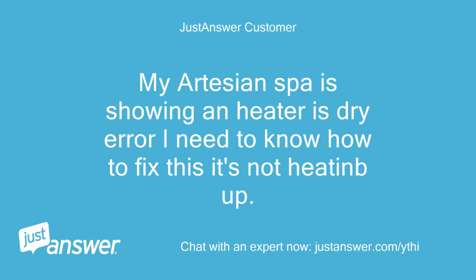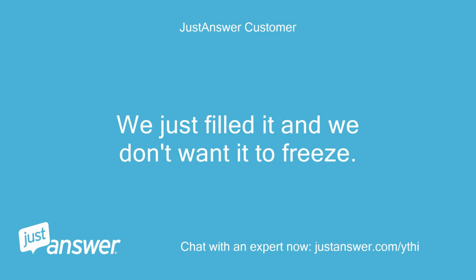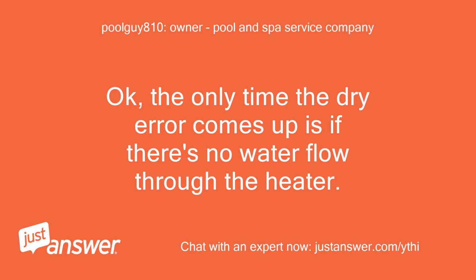My Artesian spa is showing an heater is dry error. I need to know how to fix this. It's not heating up. We just filled it and we don't want it to freeze. Okay, the only time the dry error comes up is if there's no water flow through the heater.